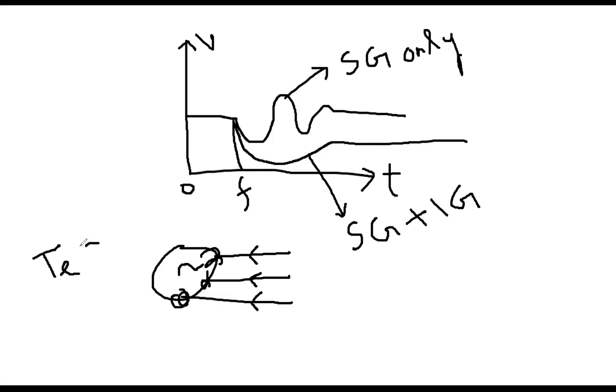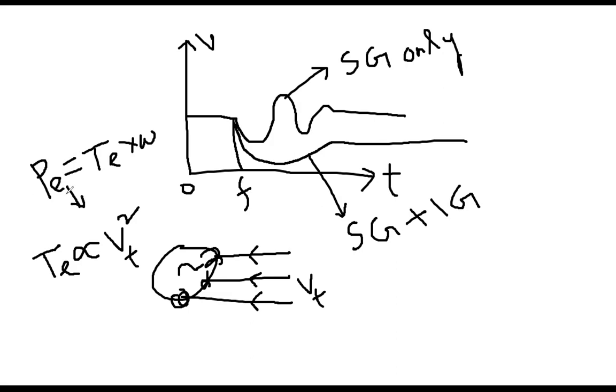Because it has gone significantly low, in case of induction machine, electromagnetic torque is proportional to voltage squared. This voltage here is the terminal voltage, Vt. So because voltage has gone significantly low, consequently your torque will go significantly low. And because torque goes low, power is torque multiplied by omega, so your output power will also go low.